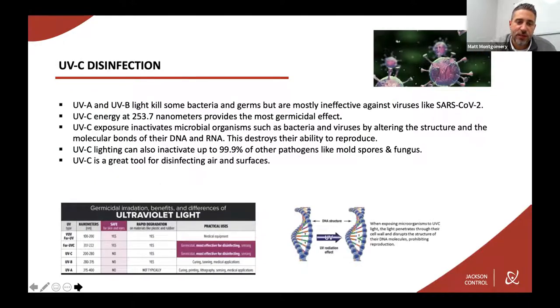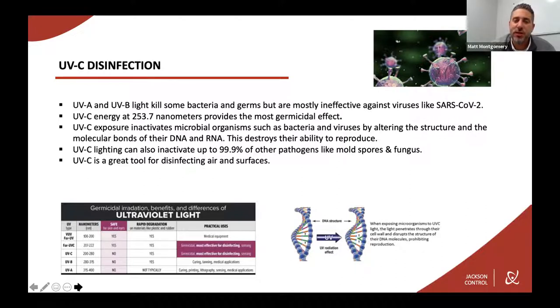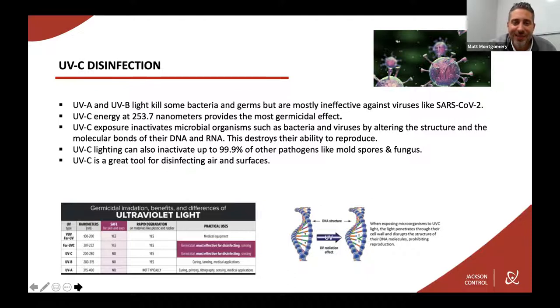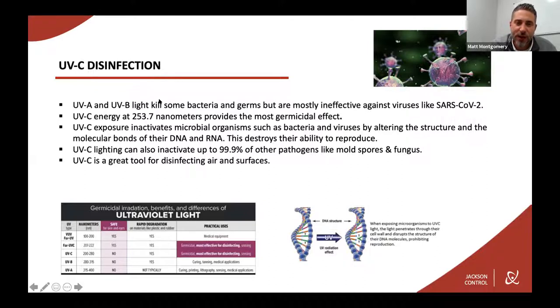UVC as it relates to disinfection: UVA and UVB light will kill some bacteria and germs but are mostly ineffective against viruses like COVID-19. UVC energy at 253.7 nanometers provides the most precise and most germicidal effect. UVC exposure inactivates microbial organisms such as bacteria and viruses by altering the structure and molecular bonds of their DNA and RNA, destroying their ability to reproduce. UVC light can also inactivate up to 99.9% of other pathogens like mold spores and fungus, and is a great tool for disinfecting air and surfaces.